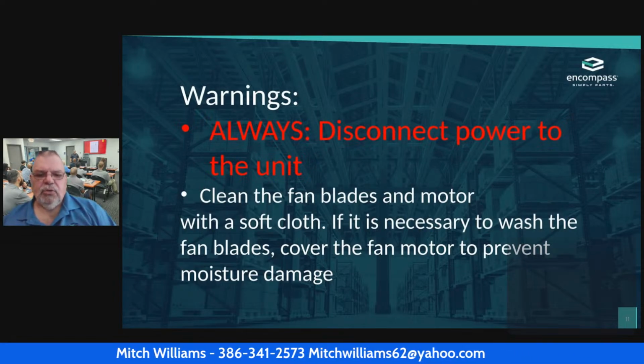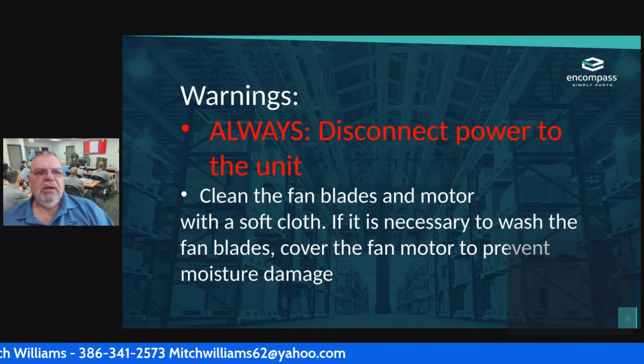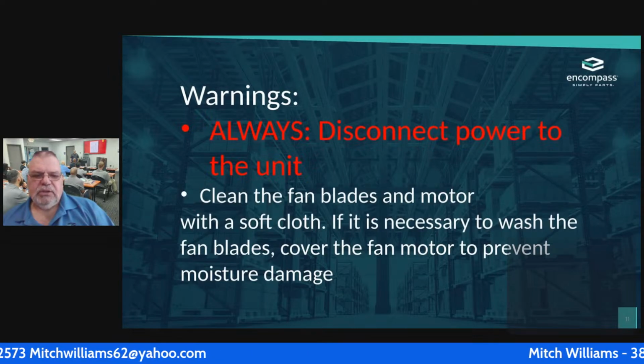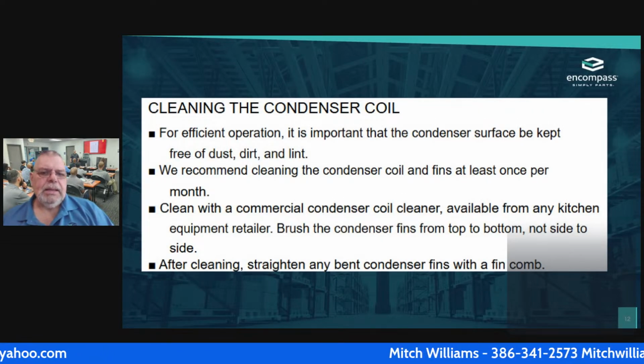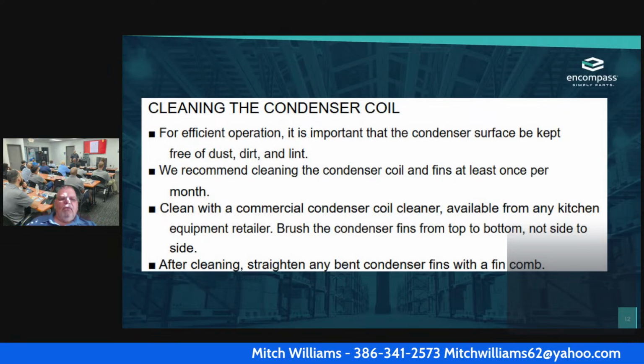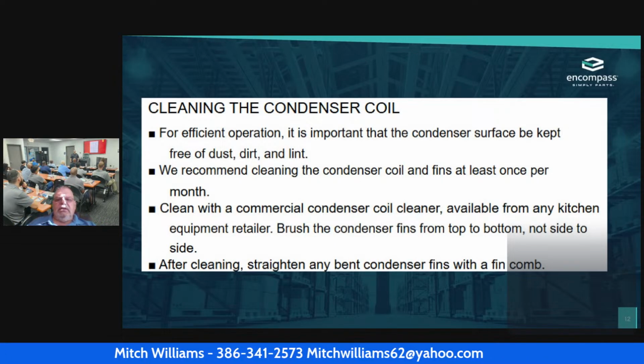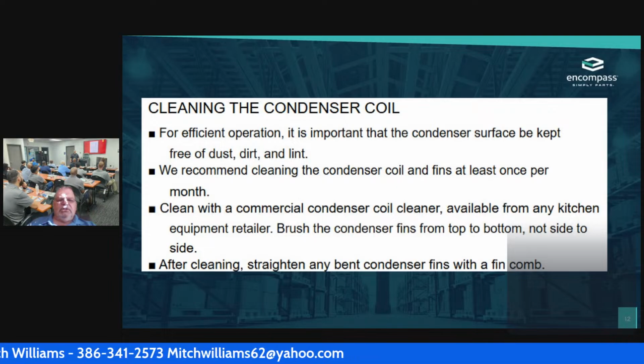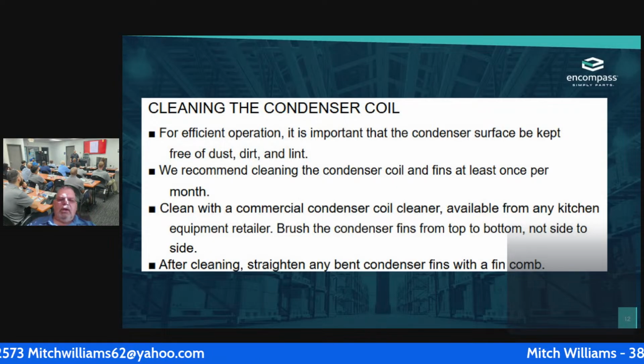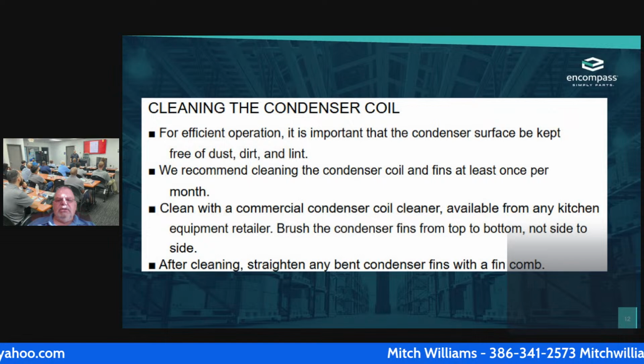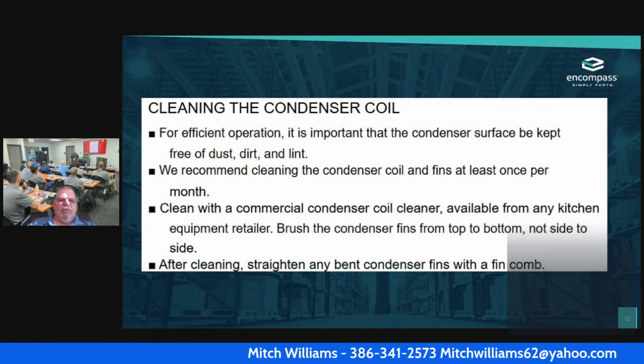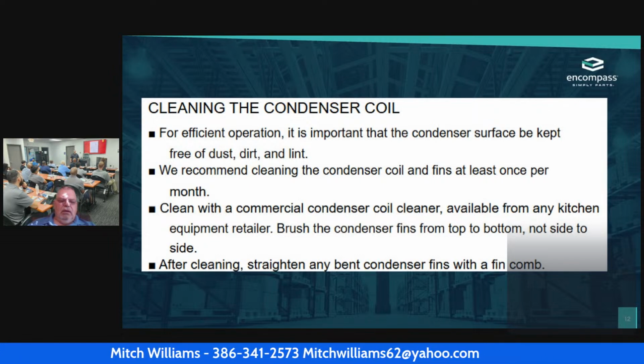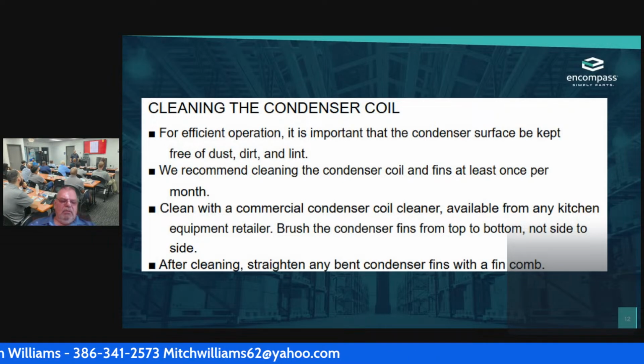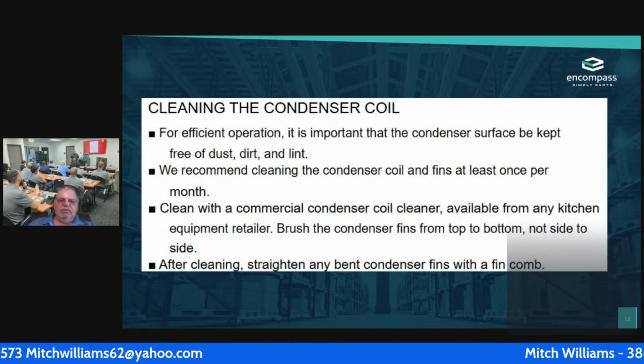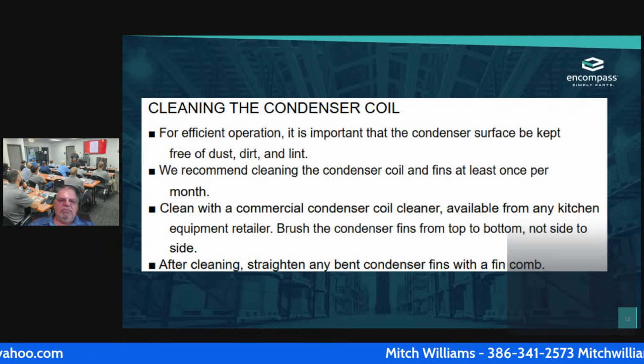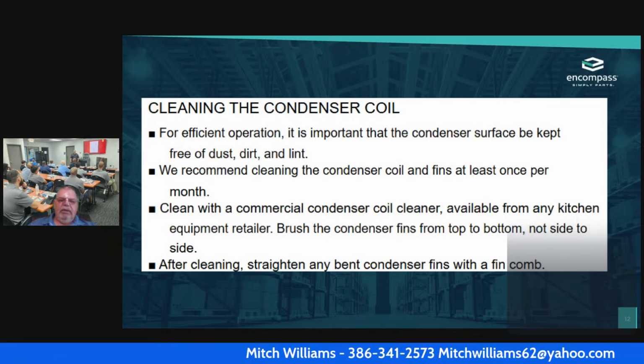So just make sure that I'm gonna cover that fan motor so that it doesn't cause any issues. Okay. Cleaning the condenser coils. For efficient operation, it's important that the condenser surface be kept free of dust and dirt and lint. They recommend cleaning the condenser coil and fins at least once a month. Once again, this is information that goes to the customer. So it tells them like 3 times that they need to clean it once a month. That's probably never going to happen.